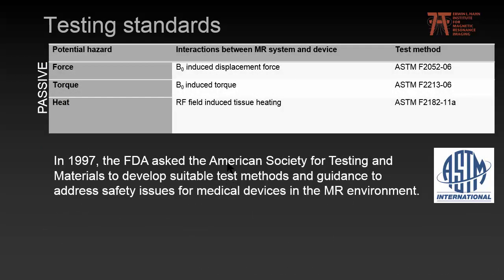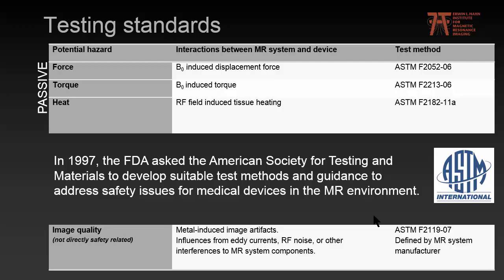In 1997, the FDA asked the American Society for Testing Materials to develop suitable test methods and guidance to address safety issues for medical devices in the MR environment. This led to three ASTM standards regarding displacement force, torque, and induced tissue heating. There is also a standard regarding image quality due to metal-induced image artifacts, though this is not directly safety-related.